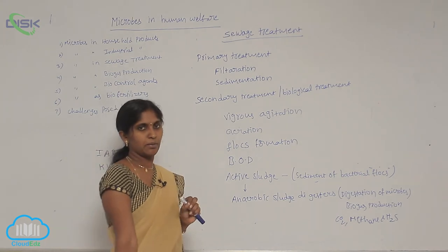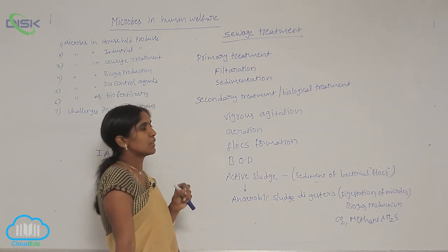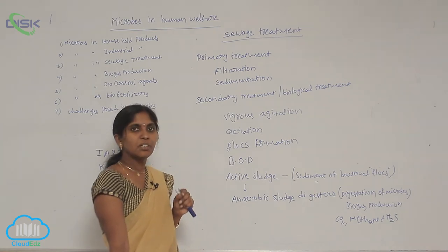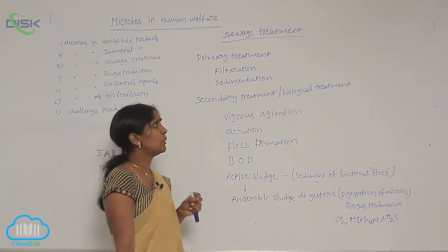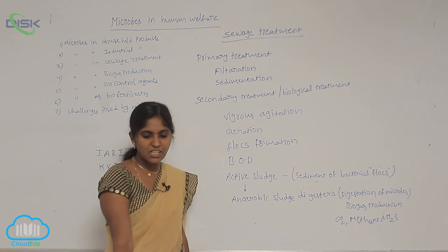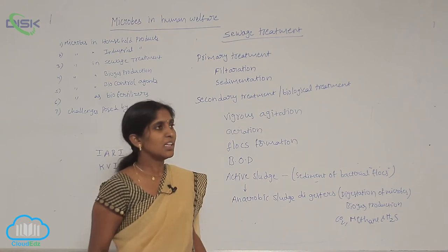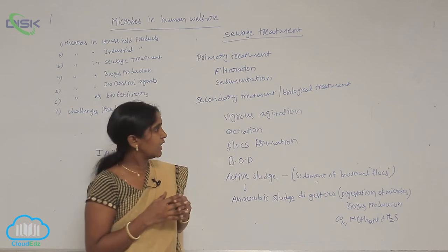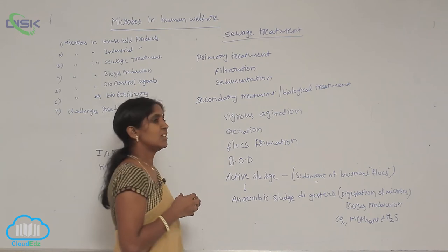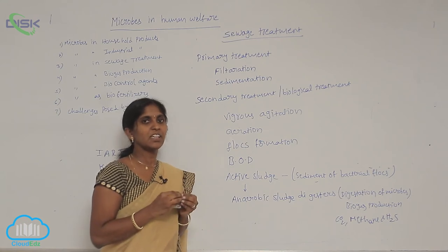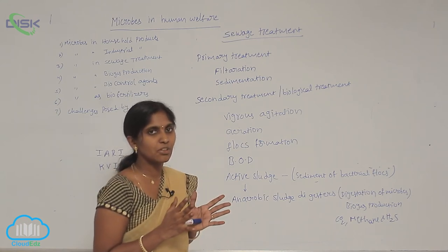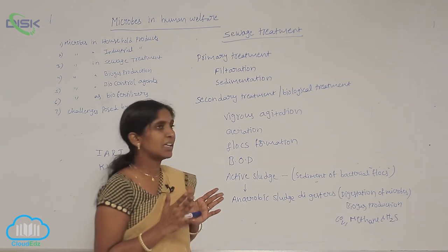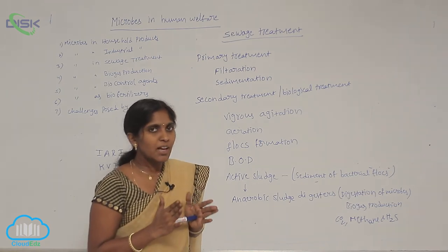The effluent from the primary settling tank enters secondary treatment. The first treatment is physical, but the second treatment depends completely on the biological activity of microorganisms. The sewage is digested with heterotrophic microbes. Different types of microbes are already present in the sewage. When they get aeration and vigorous agitation, flocs are formed — masses of bacteria with filamentous fungi that grow extensively into net-like forms, called flocs, formed in the secondary treatment tanks.